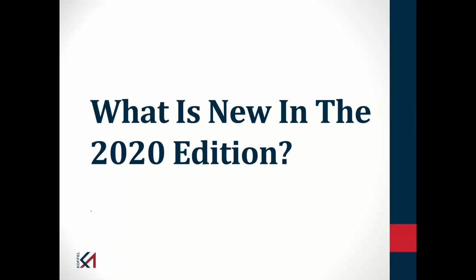Okay, let's look at a couple things that are new to the 2020 edition of NFPA 25. Before I do that, I will mention, since my objective talks about things new in NFPA 13 as well, when you transition to the 2019 edition of NFPA 13, you're not going to find anything. For those of you familiar with the standard, like I said earlier, you go to Chapter 8 for the special situations, that's no longer in Chapter 8. And it's not just a matter that things moved around, chapters got renumbered. We really restructured a lot of the content within the various chapters.